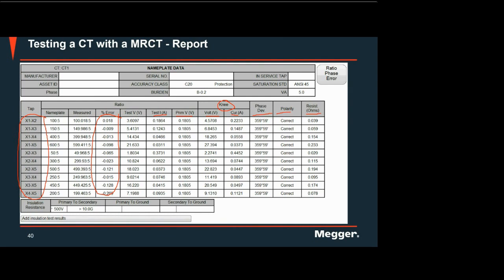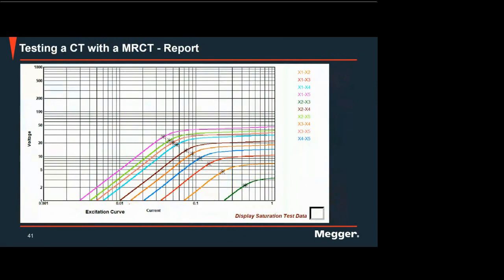Also, like I've said, we have the insulation resistance, so you can also include that one. So you can have 500 volts or more. As you can see here, at 500 volts, my insulation resistance is more than 10 gigaohm. Maybe they did not include the primary to ground here, all right? But you can also have values for primary to ground, secondary to ground. And also, this is the display of our saturation curve. So you can see multiple taps here. So you get the voltage and the excitation current here.